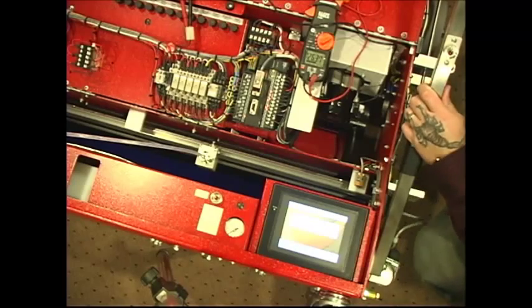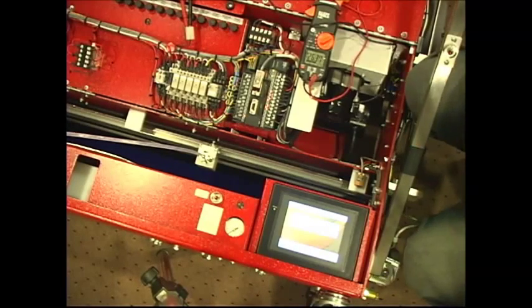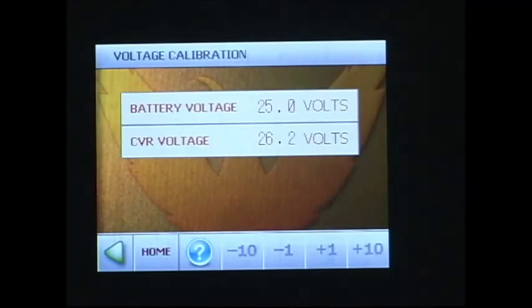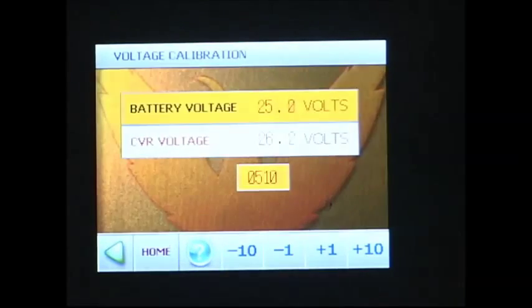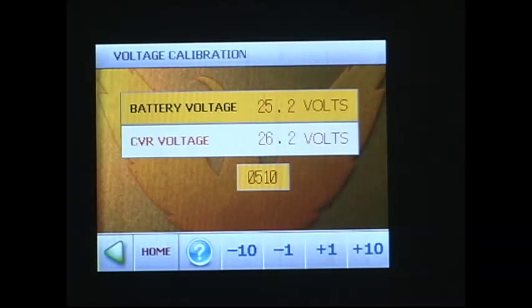This is where on the touch screen you want to make it read exactly what your voltmeter is reading. Now if an adjustment needs to be made, all you simply have to do is highlight either the battery voltage or the CVR voltage and then increase or decrease the value.